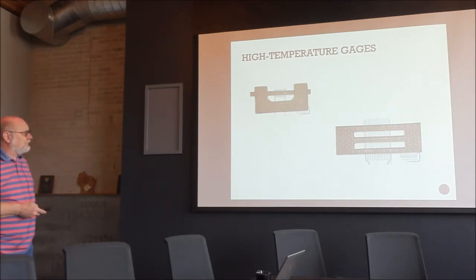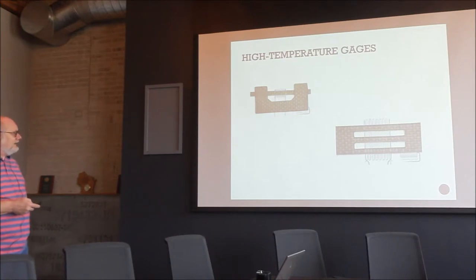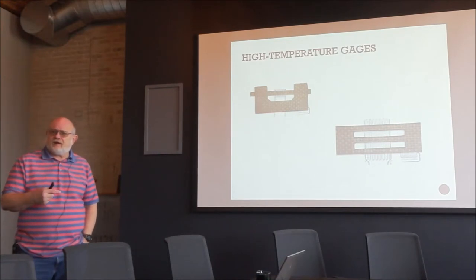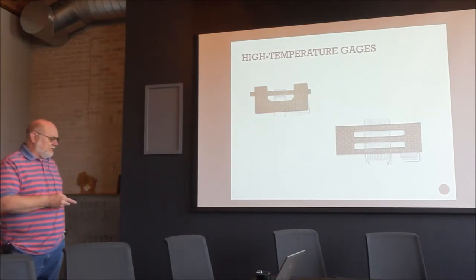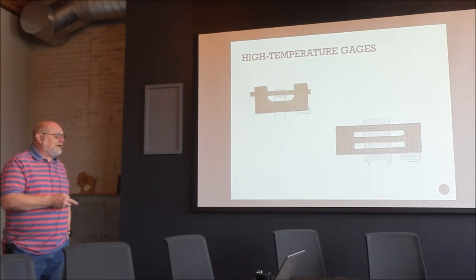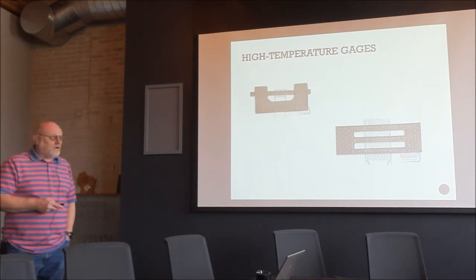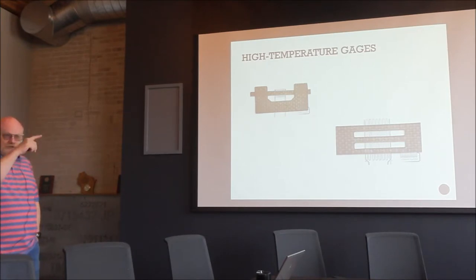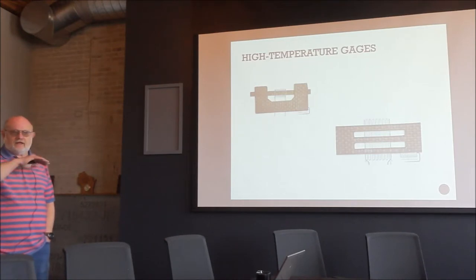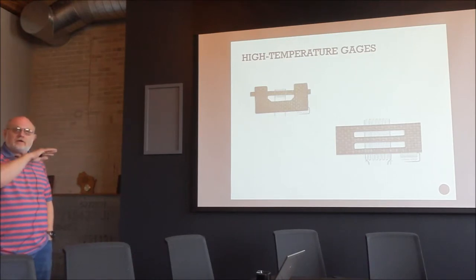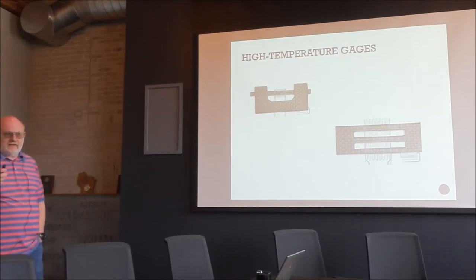Battelle developed the basic alloy for free-filament gauges: an iron-chrome-aluminum alloy with 6% aluminum, similar to Hoskins 875 but with slightly higher aluminum content. This alloy can be used above 1000°C because the high chrome and aluminum content develops a passive scale on the wire at temperature, preventing further oxidation and giving a stable alloy. Its apparent strain curve — strain versus temperature — is a very gradual S-curve due to phase transformations.